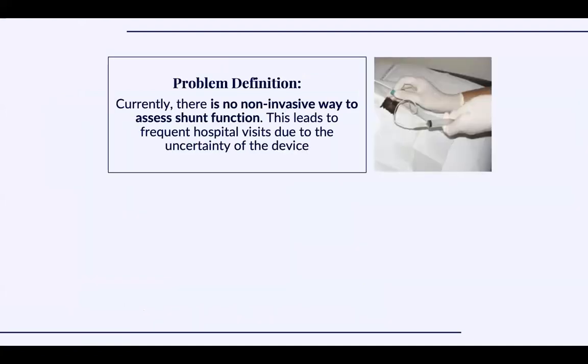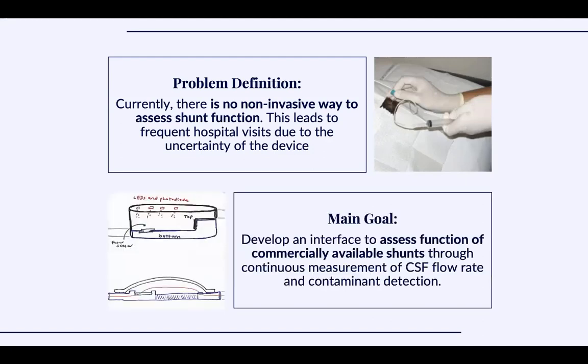Cerebral shunts have very high failure rates, which if left unrevised could lead to increased pressure, brain damage, and death. Currently there is no non-invasive way to assess shunt function, leading to frequent hospital visits due to uncertainty of the device. The main goal of the smart shunt system is to provide a non-invasive way to evaluate commercially available shunts, providing continuous CSF flow rate data and contaminant detection abilities. Using Bluetooth, this data will be sent to a patient's smart device in real time.